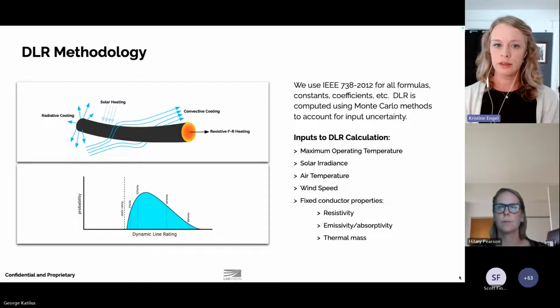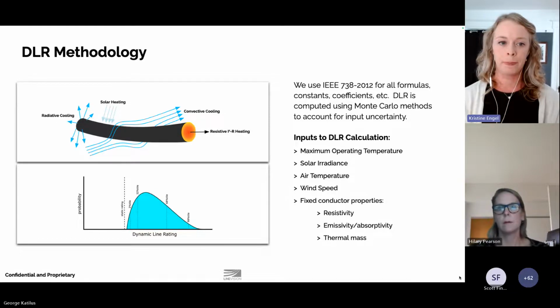That convective cooling piece is really, really important for the line rating calculation. It also is one of the hardest variables to nail down since wind can vary over short distances and short times. So when I get into the methodology next, you'll see that a lot of the work that we do is really around understanding wind speeds, specifically within the transmission corridor. And that corridor might be quite narrow, it might be sheltered by trees or other vegetation, it could be sheltered by terrain features, and those wind conditions across the entire line can change pretty dramatically.